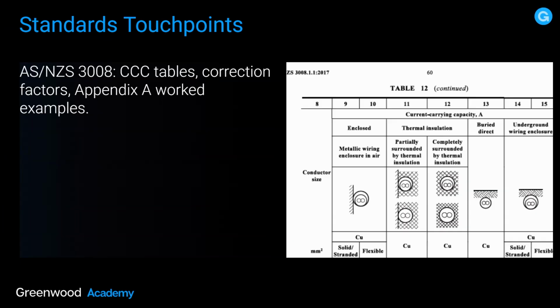Obviously, this comes with that caveat of doing your appropriate cost-benefit analysis. Standards, touch points. We're obviously going to be referencing the Australian NZS Standard 3008, and we're looking at the current carrying capacity tables, correction factors, and we're looking at Appendix A worked examples. And you can see an example here, Table 12, buried direct, column 13, in copper. Obviously, copper is going to have a different current carrying capacity than aluminium, and we're going to be looking at that. Anyone involved in any electrical work really must become accustomed to understanding these standards.